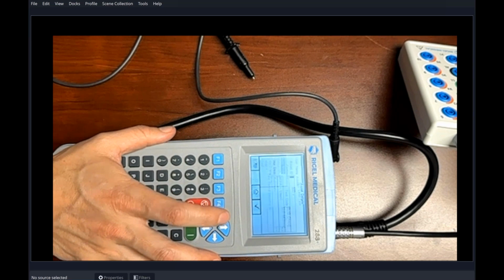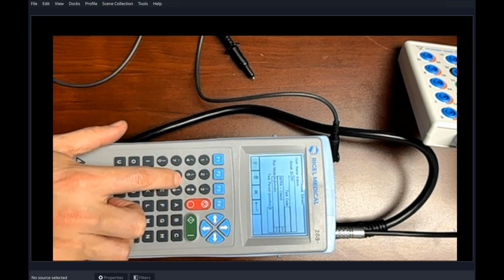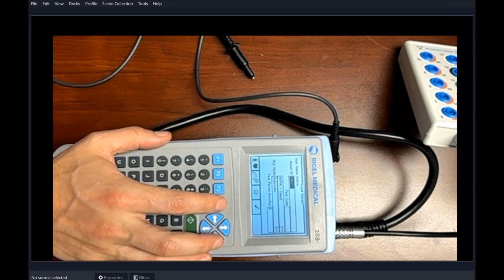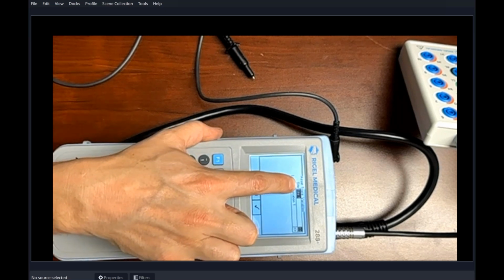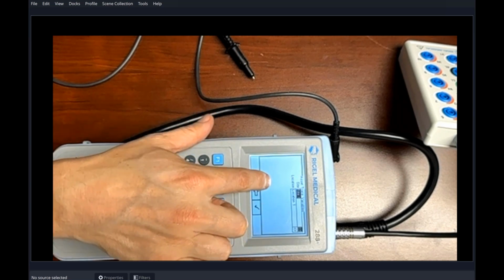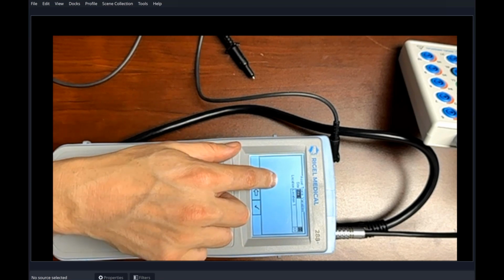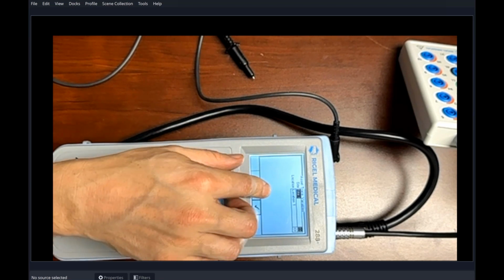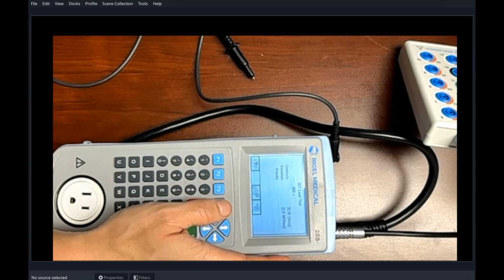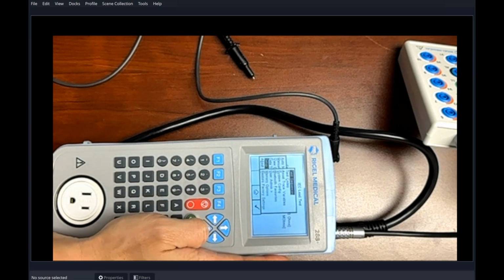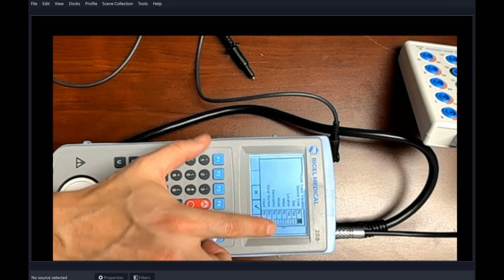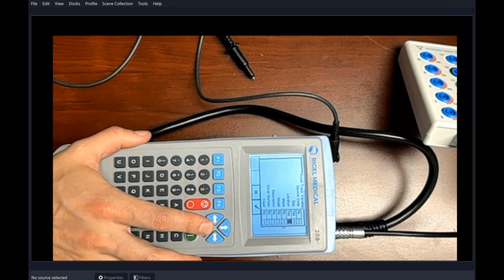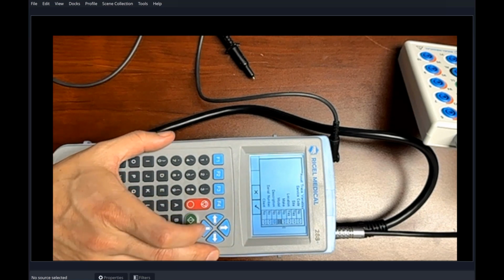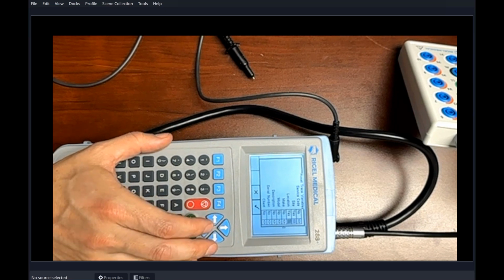And then from automatic mode, the recalling of data can be done here. So if you key in your information, the asset trace variables can be edited. So you can add additional trace variables on here, whether that be your department, the user. Additional variables can be added, and that's done within the setup of the 288 asset trace variables. And in here you can add in whatever trace variables you need for your test report. So make, model, description, serial number, client. So there's an option there to add in additional trace variables to your sequence.